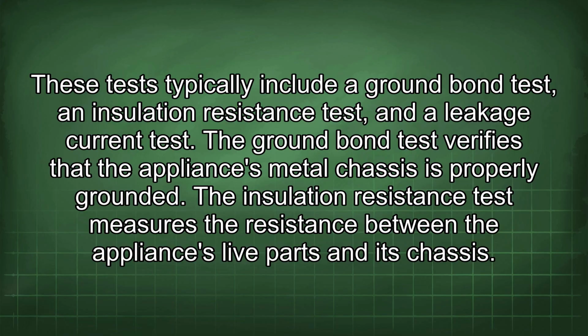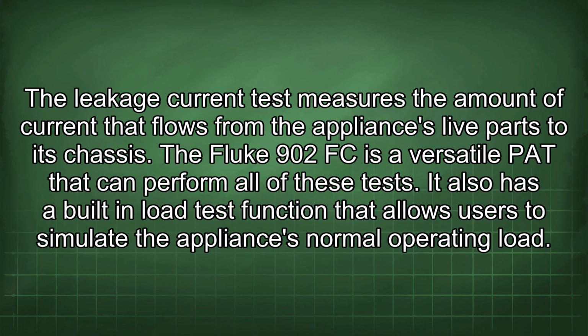The ground bond test verifies that the appliance's metal chassis is properly grounded. The insulation resistance test measures the resistance between the appliance's live parts and its chassis. The leakage current test measures the amount of current that flows from the appliance's live parts to its chassis. The Fluke 902FC is a versatile PAT that can perform all of these tests. It also has a built-in load test function that allows users to simulate the appliance's normal operating load.